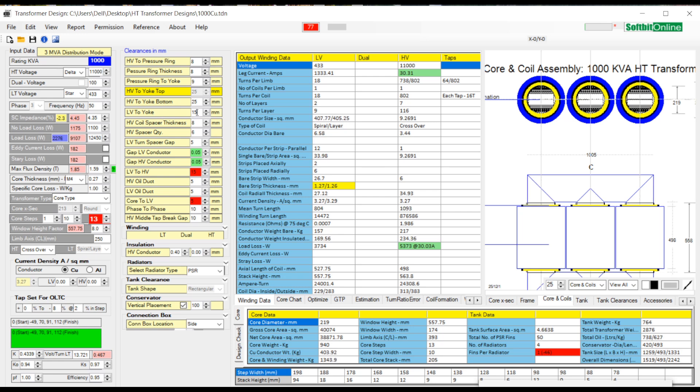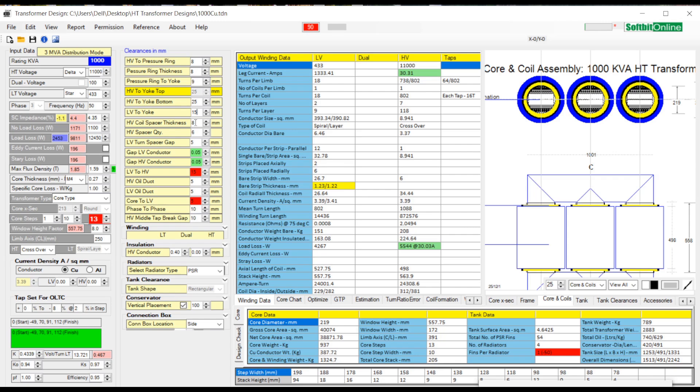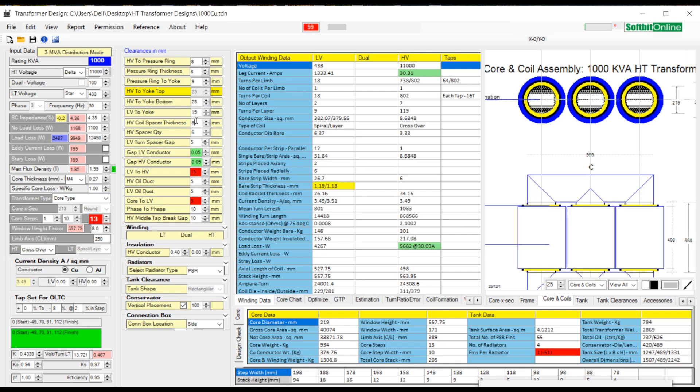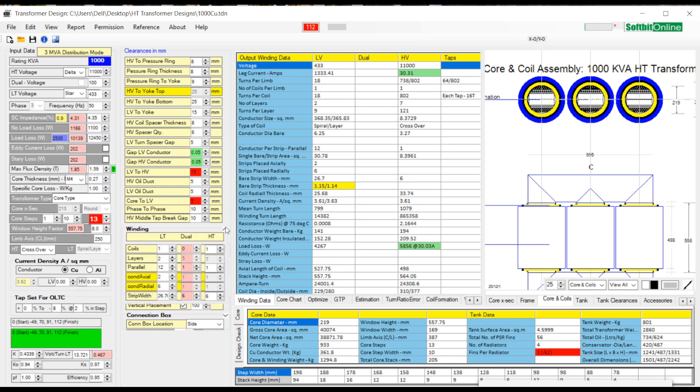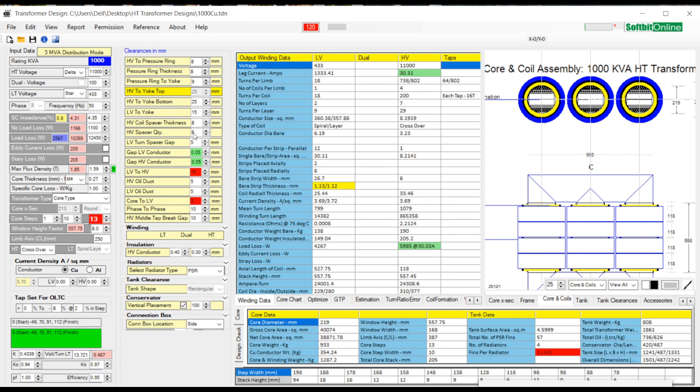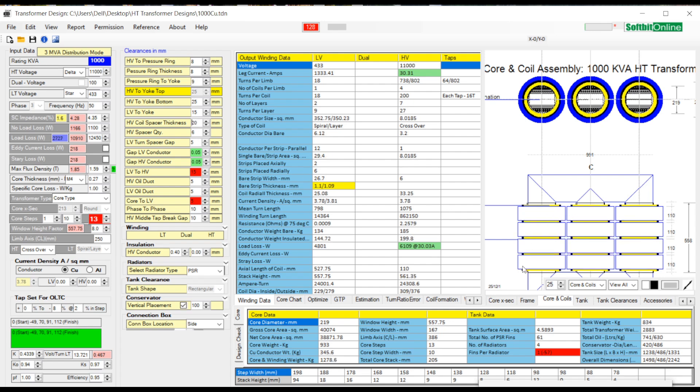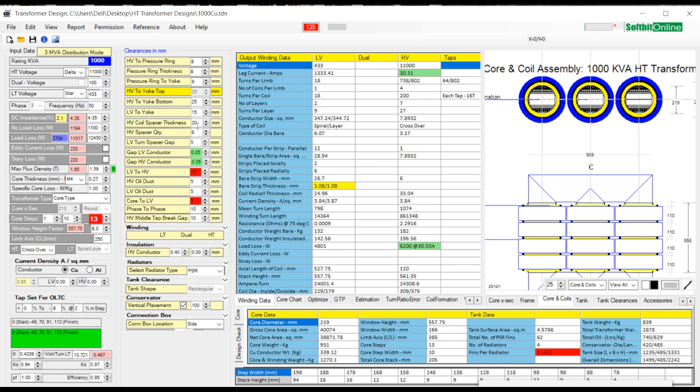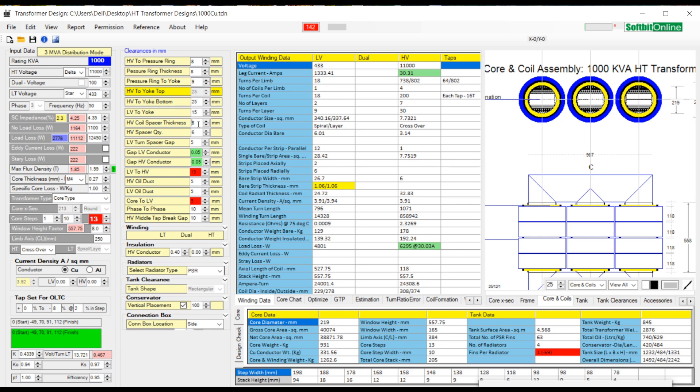If a HV leg has multiple coils like 4, 6, 8, 10 and so on, then you need to give a spacer in between each coil. This block is called a spacer. The spacer thickness is to be entered here. It can vary from 2 mm to 10 mm depending upon the kVA rating of transformer and type of winding. Crossover or disc. In foil winding no such spacer is required so make it 0.